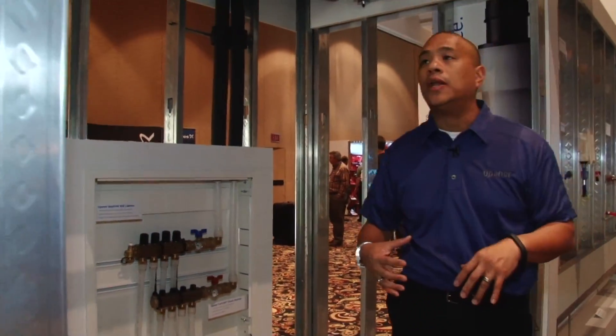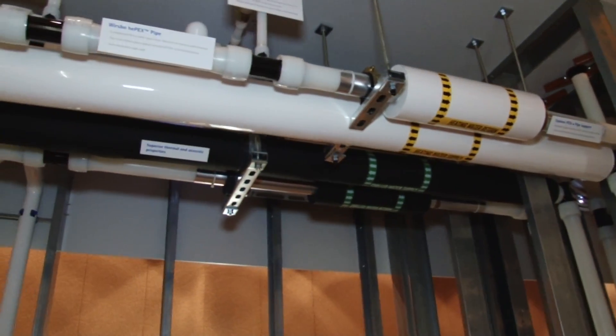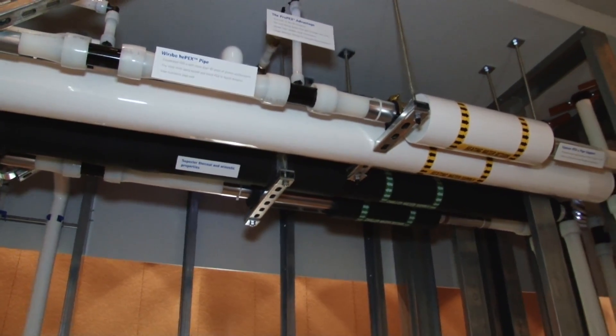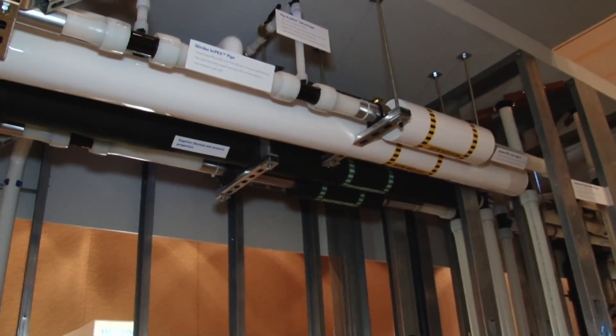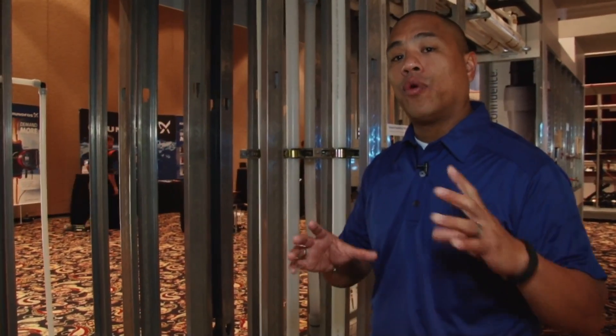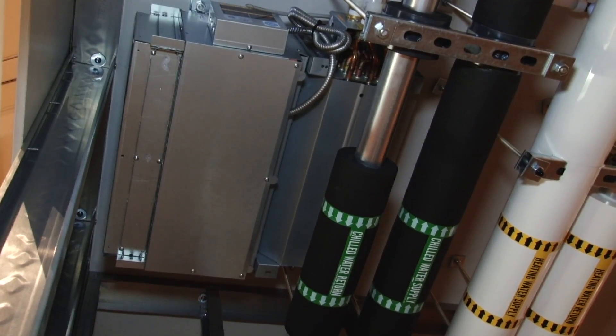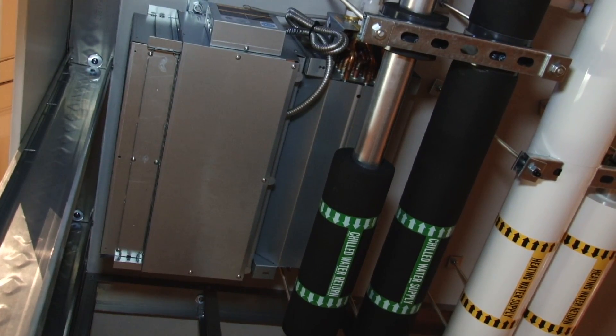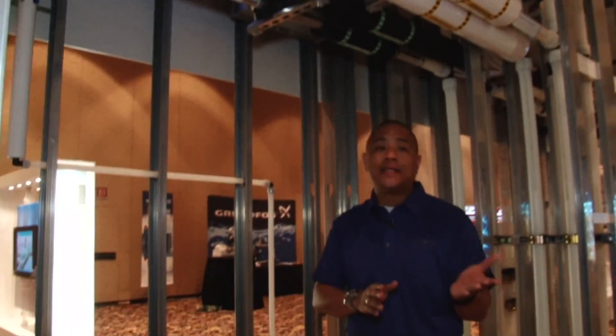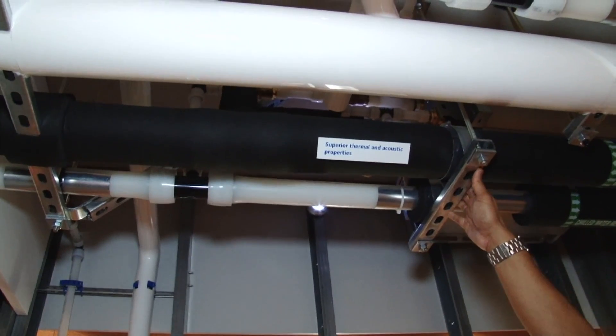It's used as part of that hydronic distribution solution. A lot of people recognize the value of PEX for plumbing as an alternative to copper, and we're starting to see that move towards the industry with hydronic distribution, using PEX for chilled water and hot water systems. Here we can see the system being used to connect to a four-pipe fan coil unit. One thing to note is that PEX tubing is copper tube size, outer dimension controlled, so a lot of the same fittings, hanger systems, and insulation systems you would use for copper, you'd be able to use for PEX as well.